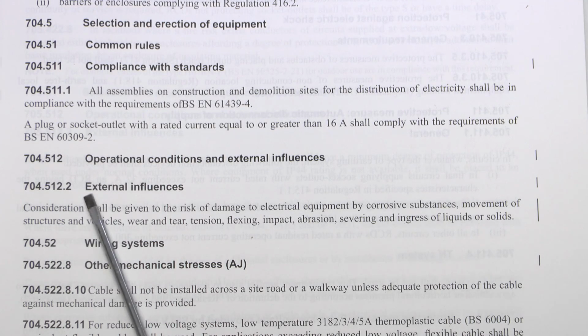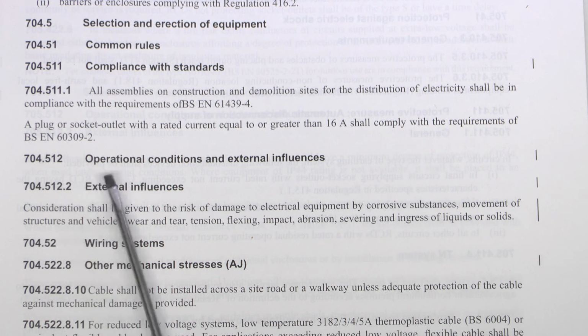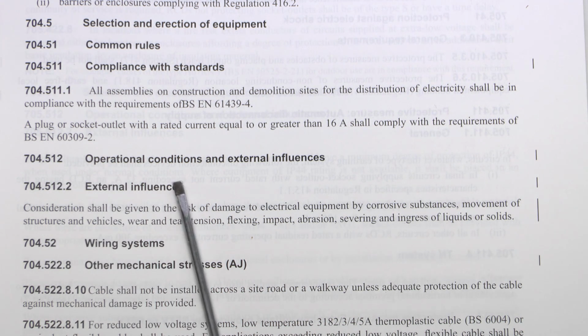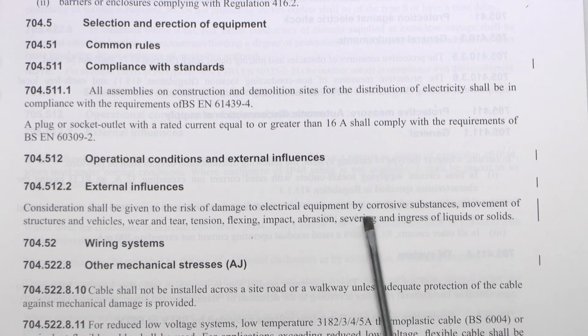The next item, which is actually new and has been added in, is 704.512.2, and that's external influences. And we've got here, consideration should be given to the risk of damage to electrical equipment by corrosive substances, movement of structures and vehicles, wear and tear, tension, flexing, impact, abrasion, severing, and ingress of liquids or solids. So this has been added in. Again, this is not something which is particularly new or surprising, bearing in mind this is based on construction and demolition sites, where all of these things are pretty much going to be inevitable in any case. So obviously just considering those items.